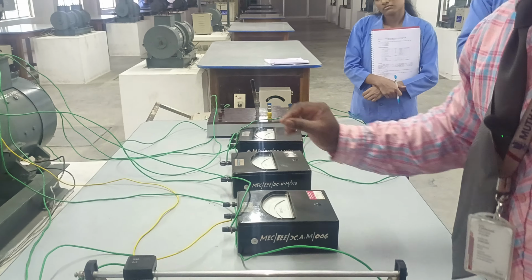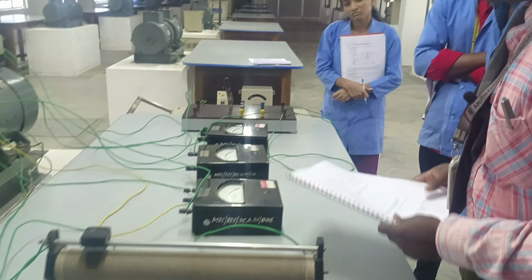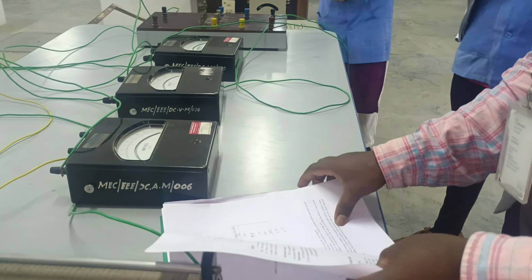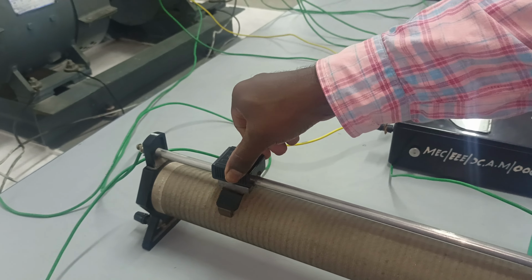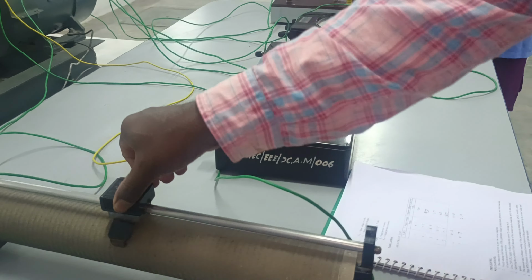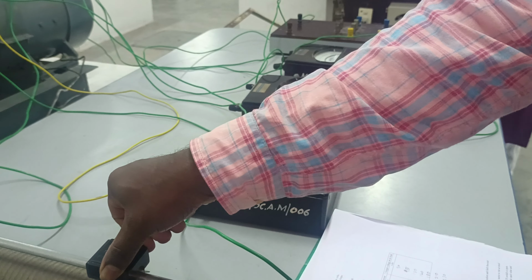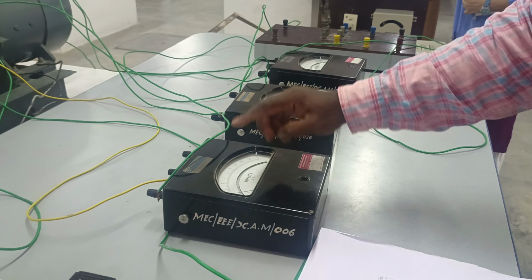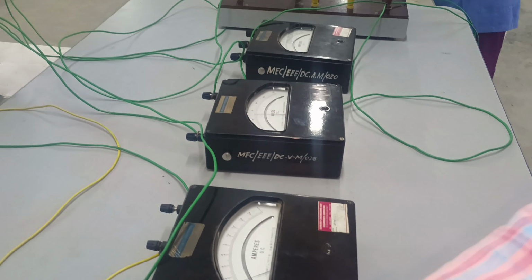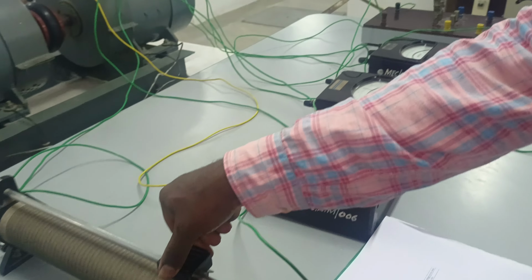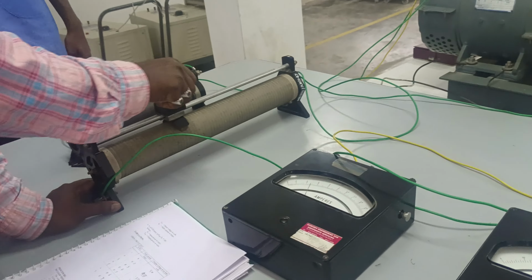We also measure the corresponding generated voltage. That is the open circuit test. Okay, the open circuit test. The readings we have noted, so we can measure it. So that was the open circuit test. Up to 0.7 we are gradually varying, and parallelly you can see that the voltmeter reading also increases while you are varying the rheostat. It means that generation has started while we are applying the field voltage.